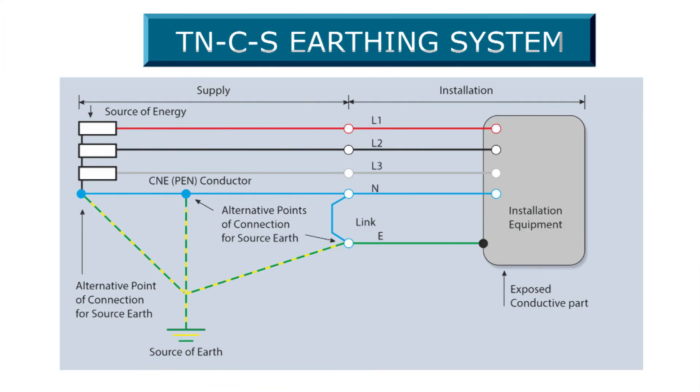Finally, the TNCS earthing system: the neutral and protective earth are combined into a single conductor in a part of the system. This type of earthing is also known as protective multiple earthing. The supply system PEN conductor is earthed at two or more points, and an earth electrode may be necessary at or near the consumer's installation. All the exposed conductor parts of the installation are connected to the PEN conductor via the main earthing terminal and the neutral terminal, and these terminals are linked together.